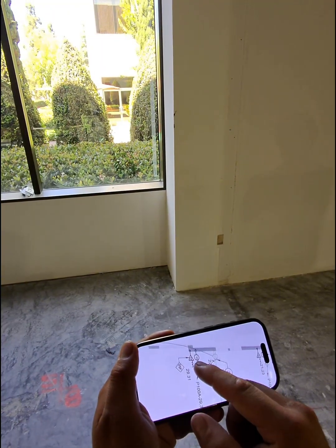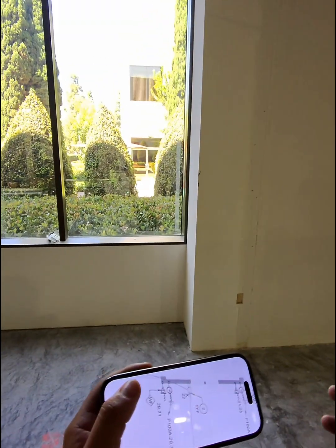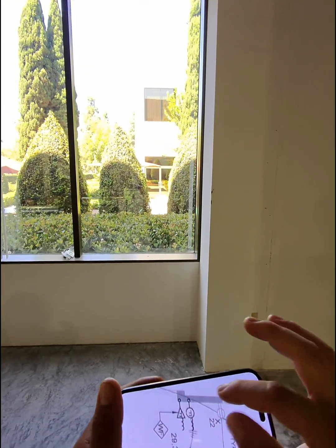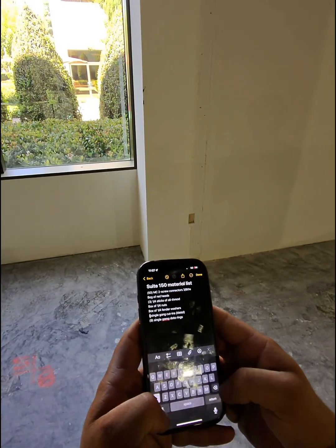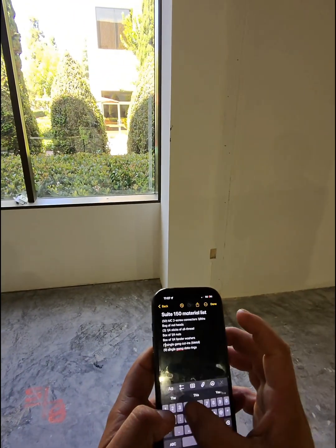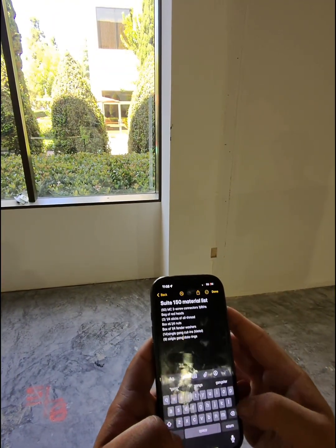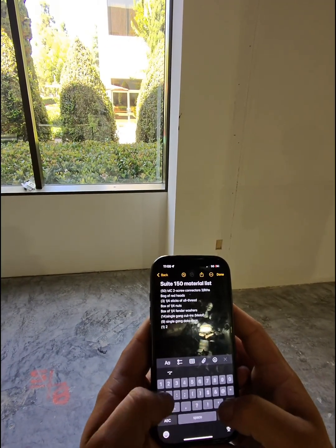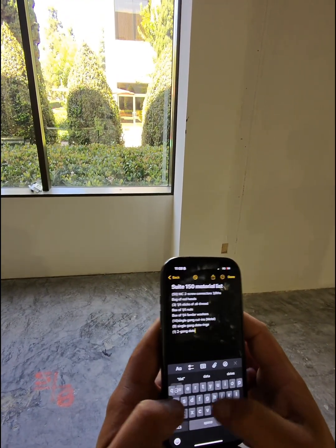This is a furniture whip. These are like a cord that goes into furniture, like those cubicles you see in movies. Usually they're 2 gang. This is a 2 gang metal cut-in box. This would be a 2 gang data, so I'm gonna add that onto my list. For 2 gangs, it's just 2 single gang outlets put together, so I just count it as 14. But for the data rings, you have to specify 2 gang data ring because they come pre-built. Can't combine them.